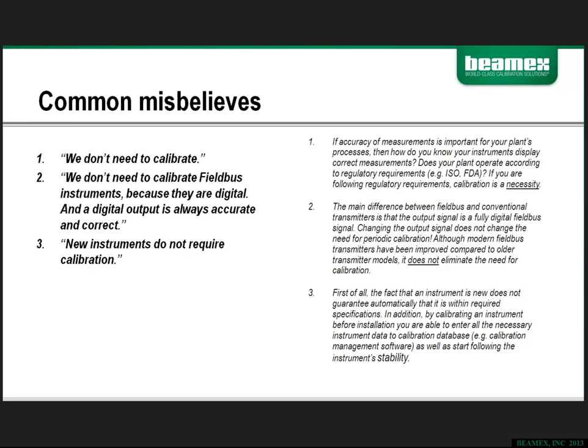Secondly, we don't need to calibrate field bus instruments because they're digital, and the digital output is always accurate and correct. There have been a lot of improvements in transmitters. Digital field bus signal is indicative of one of those. However, field bus instruments are just as likely to be affected by drift over time as any other instrument. They still require periodic calibration to ensure that they are accurate.